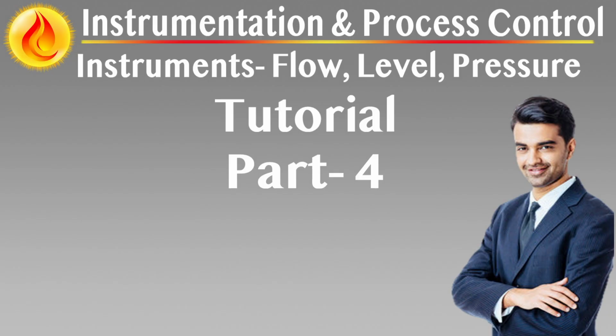Service limitations and suitability screening. These meters work best with clean, single-component gases with minimal variability in thermal properties, stable temperature environments with dry, non-condensing flows. They are not recommended for multi-phase flows or gas with liquid carryover, e.g. saturated or condensing streams. Applications with rapidly changing composition, such as biogas or mixed process off-gas, highly corrosive or particle-laden gases without protective coating or filters. Free liquids on the heated sensor will falsely spike flow readings or damage the probe. For saturated services, upstream filters, knockout drums, or condensate traps are essential.